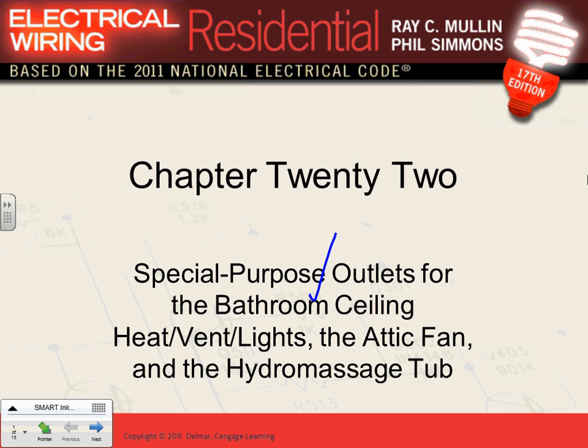Or you can feed the lighting in the bathroom from another circuit in the area. That's what I want you guys to do for our project. If you're only having a lighting fixture there, I want you to feed it from the lighting circuit in the area. Now the exhaust fan, the same thing. You can feed the exhaust fan from the 20 amp dedicated circuit. If it's a big combo like the one that you're going to be looking at, more than an exhaust fan, it heats, it gives you light, and it exhausts. That's a combo. This one will need what? A dedicated 20 amp circuit.